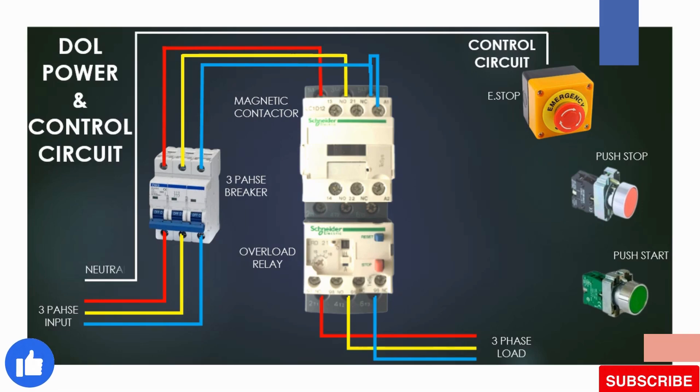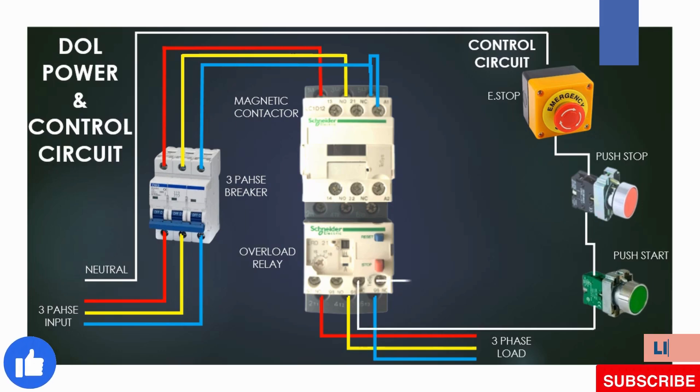The wire goes to the E-stop, then the off push button and the on push button. After that it goes to the overload normally closed point, and from the second point of the overload we connect to the contactor coil A2.